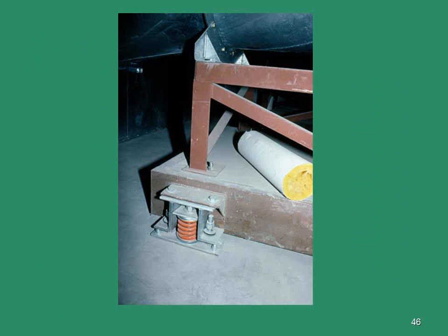What did you do on the federal building? Well, what we did on this building is, ultimately, none of this enclosure was there in the first place. We built this enclosure around it, with air intake through the silencers and air exhaust through the louvers, and it even had to have a roof on it because of the homes up on the hill. So all of this stuff you see is noise control added just to take care of this one cooling tower, and that's been a while. It worked. At that point I could measure 50 decibels at night at the property line, the judges were satisfied, and we didn't spend the month in jail.